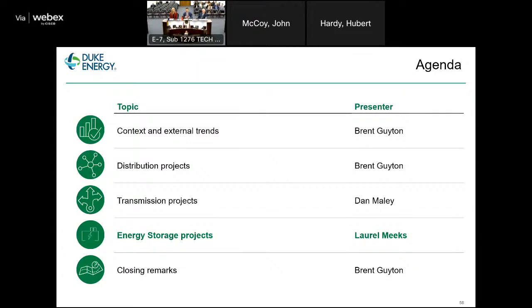Some generation retirements really result in very minimal changes or impacts to the transmission system. We're able to keep the switchyard at the current location, or the substation that's essentially on site at the generation plant, and still use that as an asset to route power around, just without the associated generation coming on. Allen is an example where that didn't work for some specific reasons under our planning model, so we needed to actually move it. But I wouldn't say every generation retirement requires a significant project scope on the transmission grid. There will be some changes, but not necessarily significant ones.